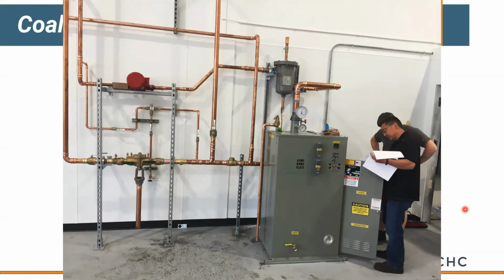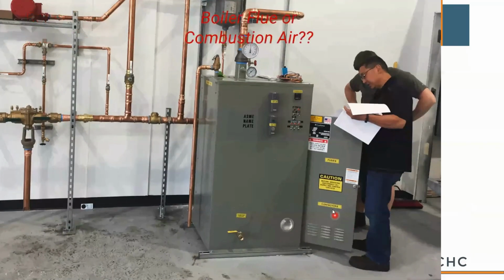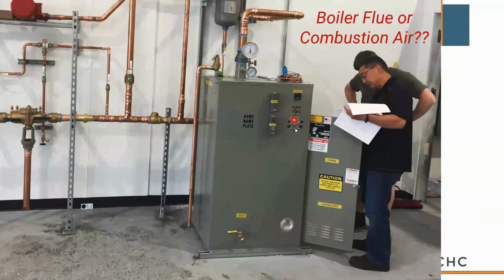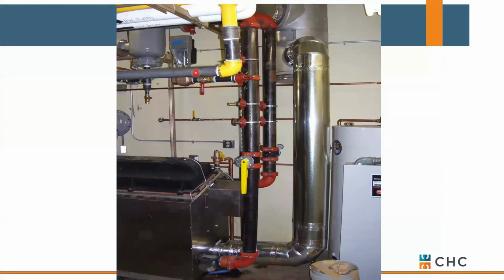One thing we're seeing a lot these days is a move to electric boilers. And one thing you'll see with electric, there's a lot of contactors, a lot of steps, but you will not see boiler flue or combustion air. So when you look around this boiler, you'll notice that there's no vent pipe. There's also no ducted combustion air because it's electric. You don't need that. The meter is going to spin like crazy when the boiler fires, but you don't need to vent it.